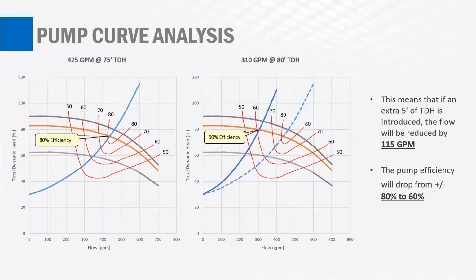But what happens if things change? What happens if we get obstructions in our force main? What happens if valves are partially closed? That system may be operating completely differently than originally intended. If you look to the curve on the right, that's the same pump curve, but you can see the system has changed because of some sort of issue in the force main system.